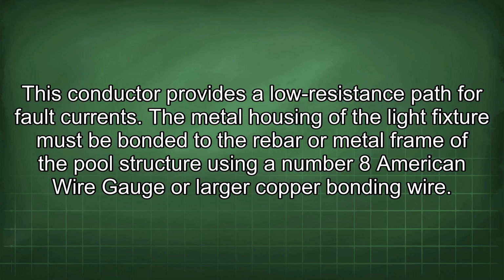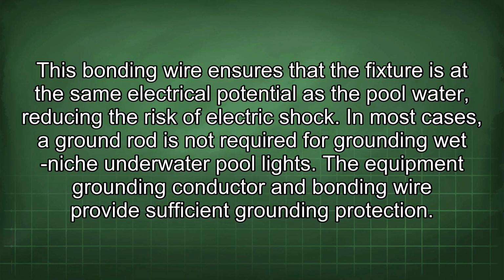The metal housing of the light fixture must be bonded to the rebar or metal frame of the pool structure using a number 8 American wire gauge or larger copper bonding wire. This bonding wire ensures that the fixture is at the same electrical potential as the pool water, reducing the risk of electric shock. In most cases, a ground rod is not required for grounding wet niche underwater pool lights. The equipment grounding conductor and bonding wire provide sufficient grounding protection.